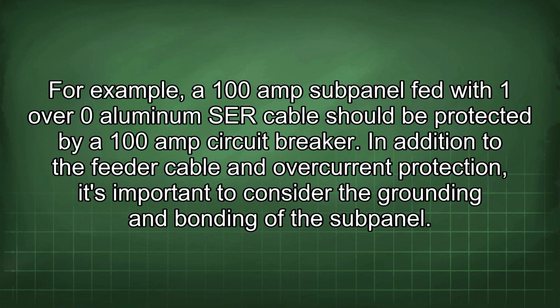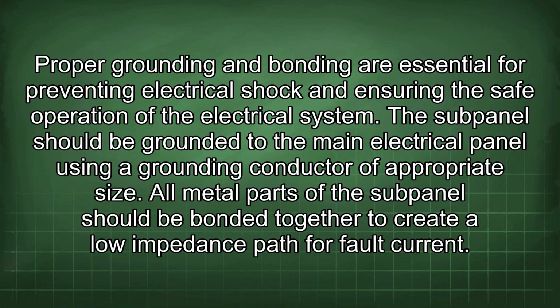breaker. In addition to the feeder cable and overcurrent protection, it's important to consider the grounding and bonding of the subpanel. Proper grounding and bonding are essential for preventing electrical shock and ensuring the safe operation of the electrical system. The subpanel should be grounded to the main electrical panel using a grounding conductor of appropriate size. All metal parts of the subpanel should be bonded together to create a low impedance path for fault current.